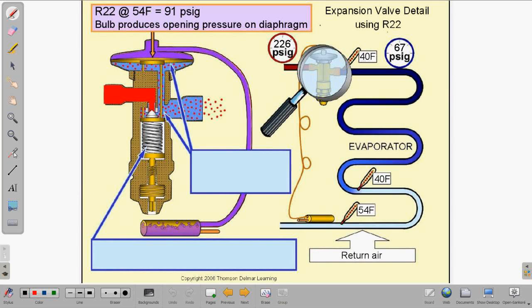All right, so let's take a little bit of time and explain what we're looking at here. We have two different views here, one of the TXV and then one of the evaporator circuit. So the little magnifying glass here is depicting the cutaway of the TXV valve, and we'll go through this one by one. So here's our sensing bulb, and it is mounted to the outlet of the evaporator coil. And inside of the sensing bulb is usually the same type of refrigerant that is in the system. So in this example, we're using R22. So the TXV valve would have R22 refrigerant in the sensing bulb itself.